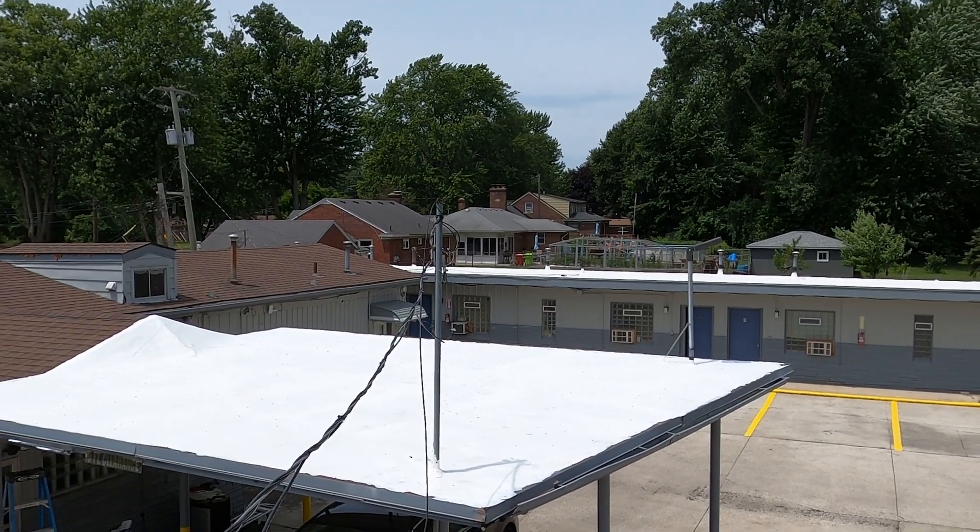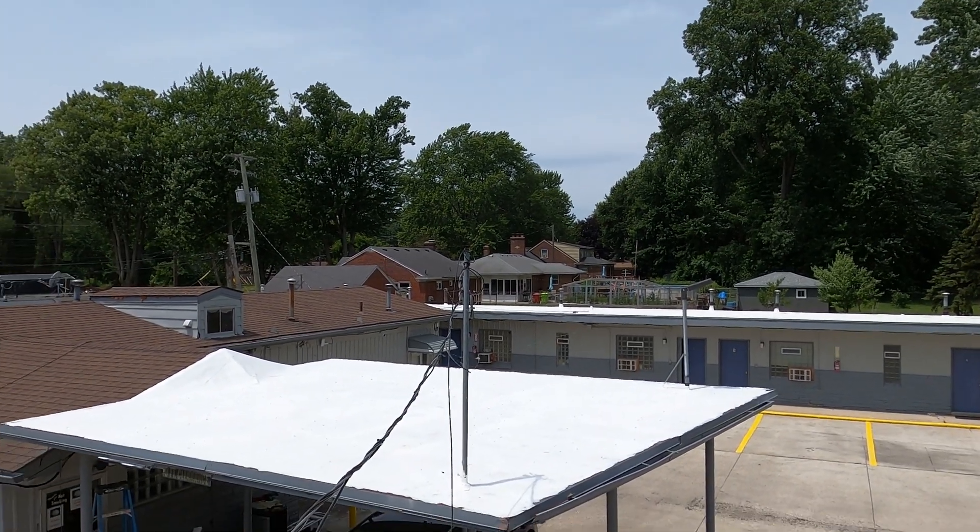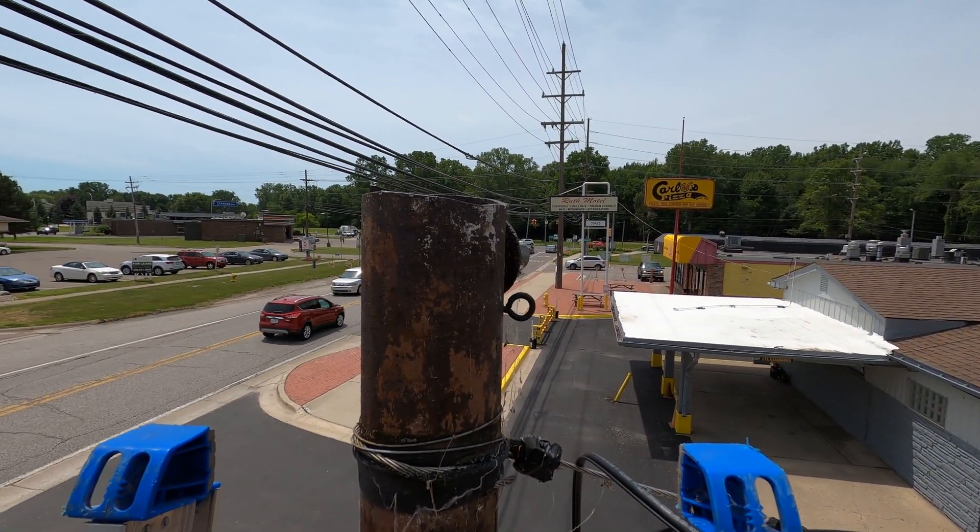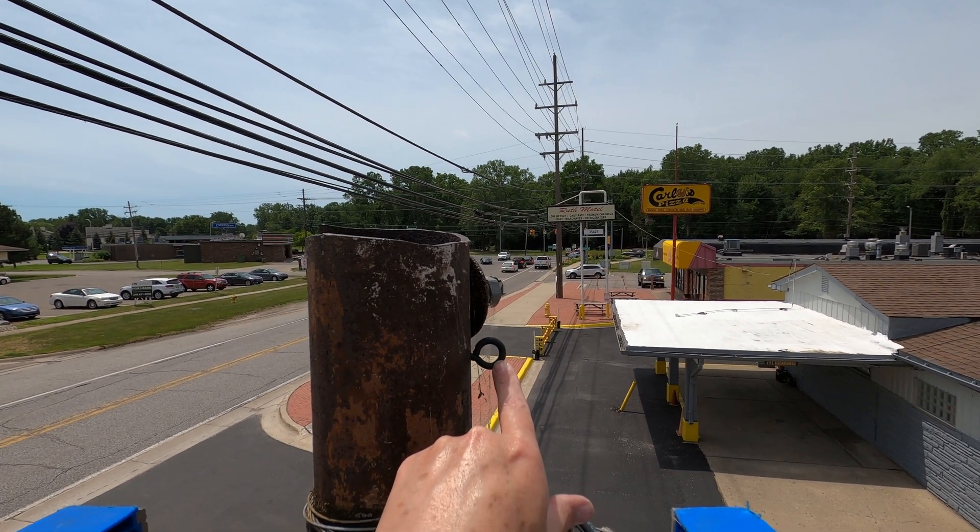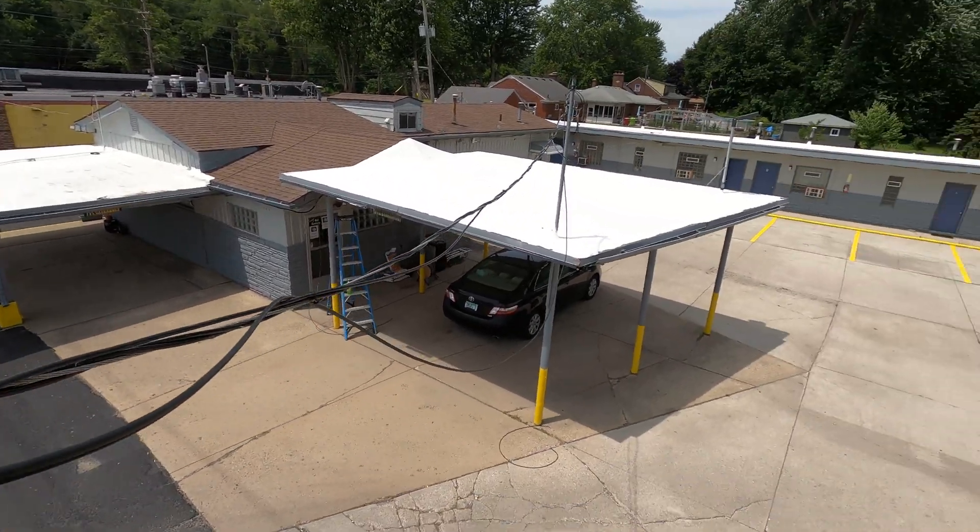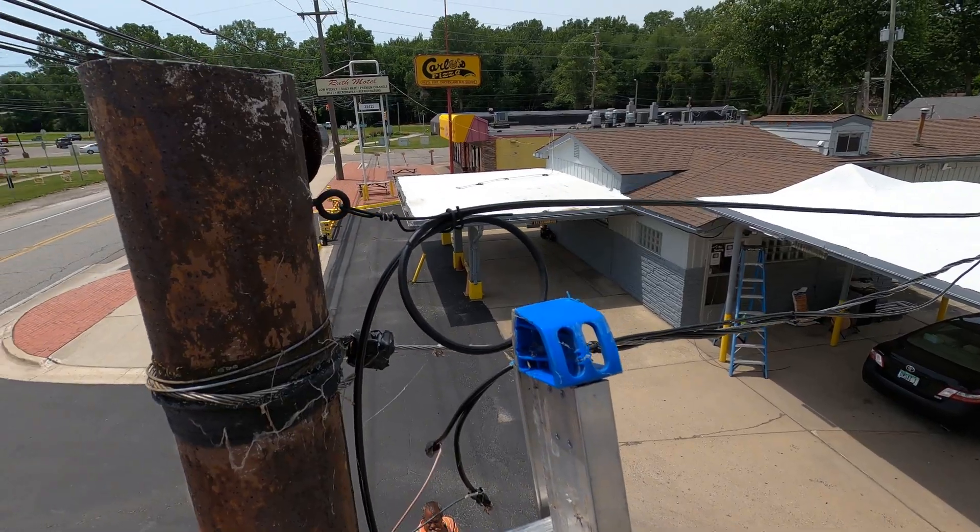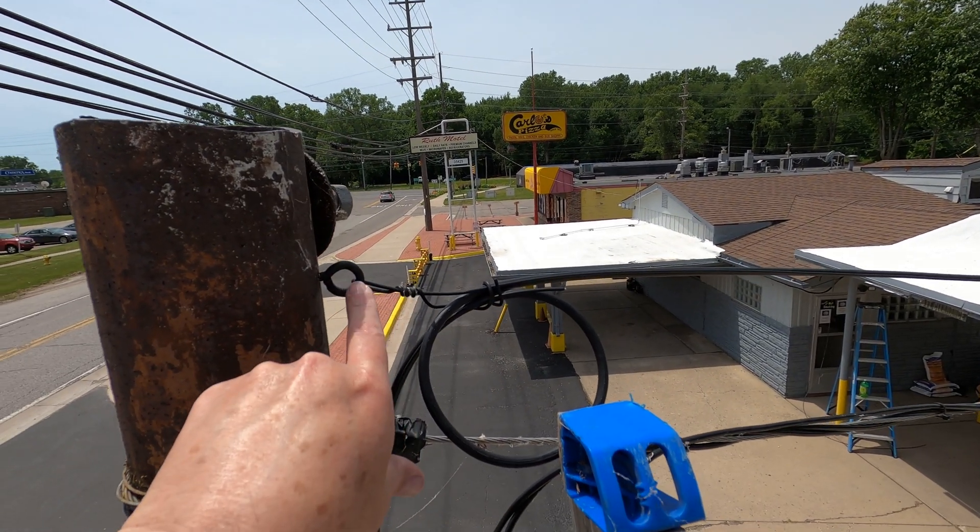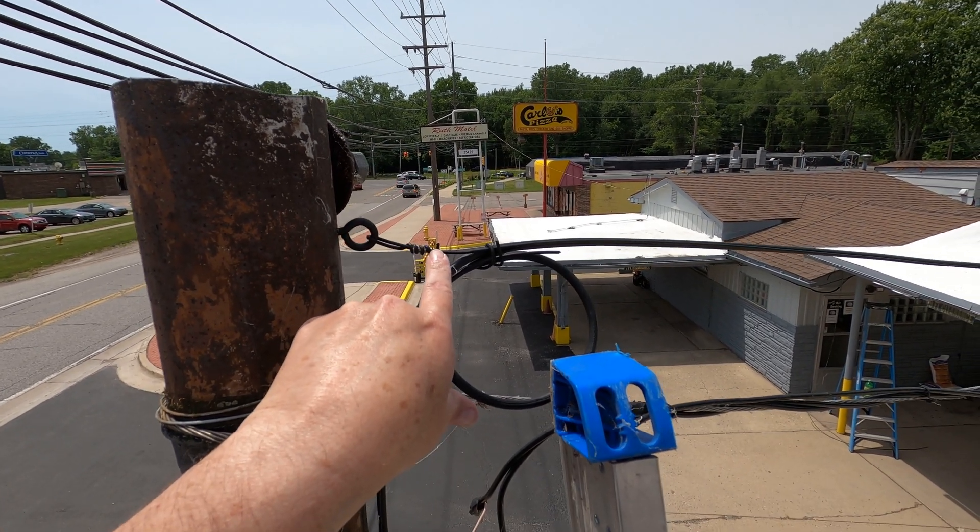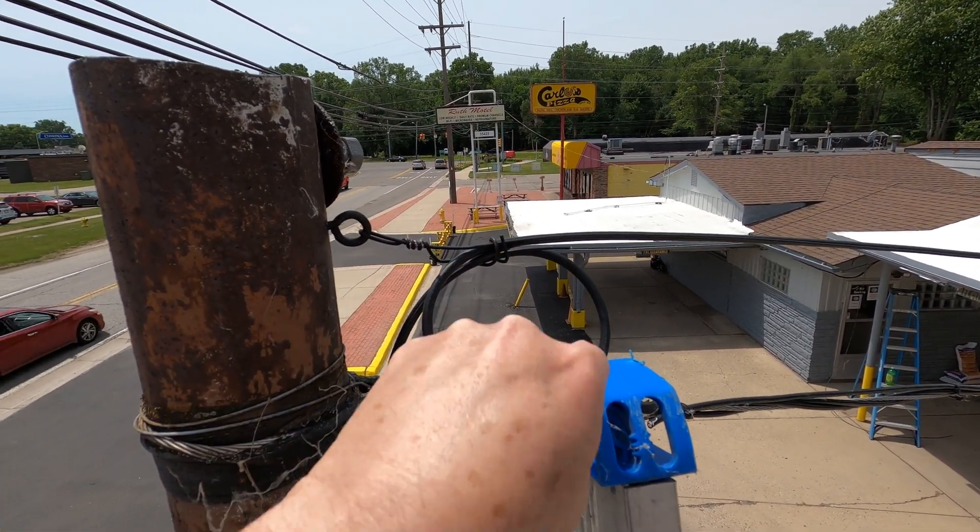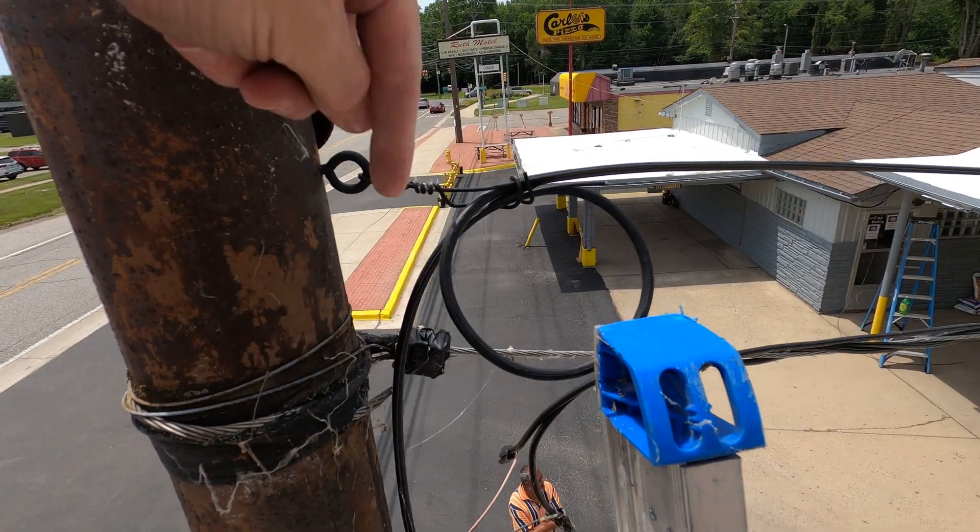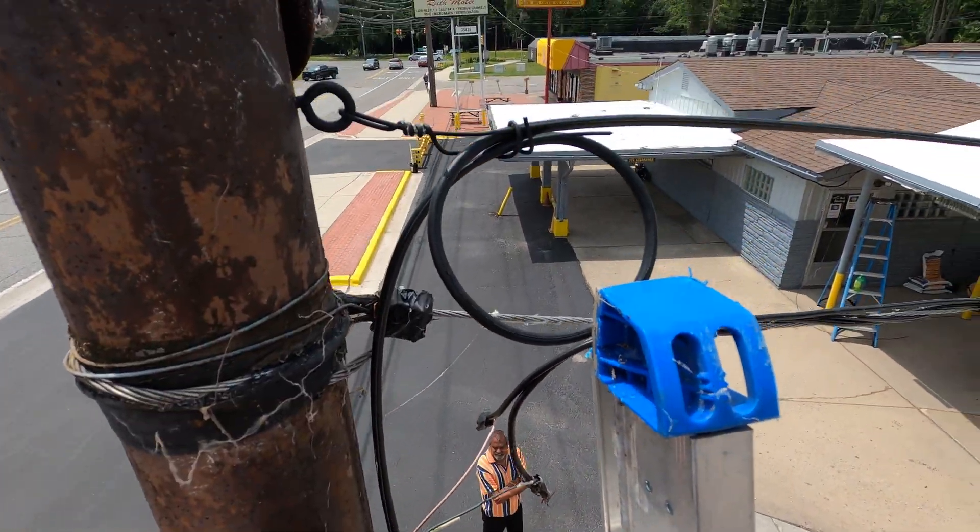So that's where I was at and you can see where the messenger wire is attached. And now the messenger wire is hanging and I'm at the opposite end all the way up. I'm on a very tall pole here. We've got an eye hook installed and it's ready to get the messenger wire attached right here. And then the wire is going to continue down. So as you can see, I am up quite a ways. All right, we have success. The eye hook has been threaded through. I've got at least three and actually almost nearly four wrap arounds. And then I did my loop. That's at least four inches in size and diameter. And then I took the excess messenger wire and wrapped it around to retain it. Then it's going to go out and run on down and it'll get terminated to a camera.